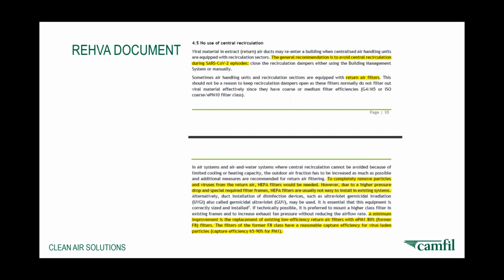So they're saying that to completely remove particles and viruses from the return air, HEPA filters will be needed. I agree. But unfortunately, due to the higher pressure drop and sometimes special required frames, they may not be easy to install on existing systems. So again, if you're looking at installing HEPAs into a system, and this is not an advertisement for any company, but Camfil, the company with whom I work, have carried this out in many, many hospitals and other environments over the years. So advice is available from us and from other industry specialists.